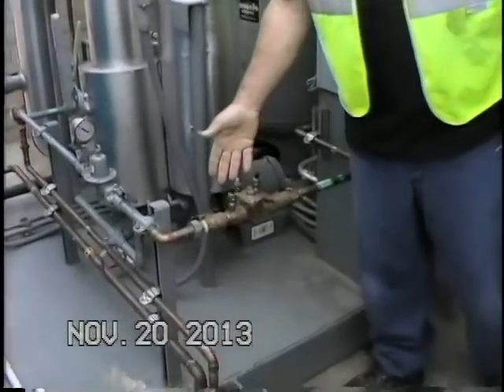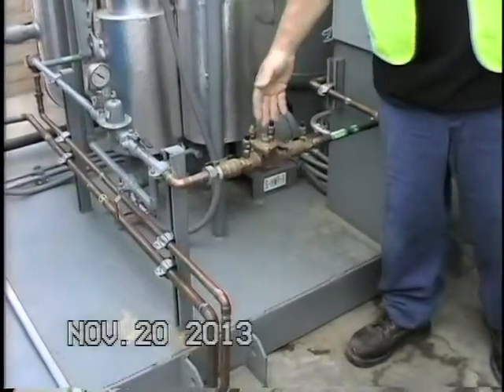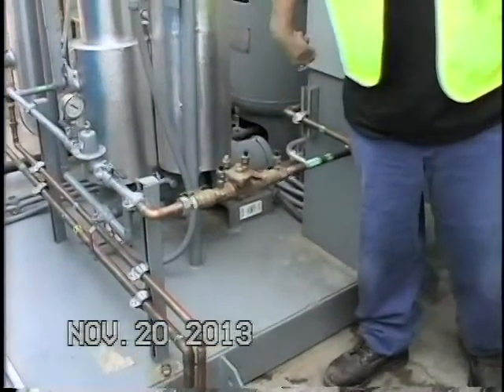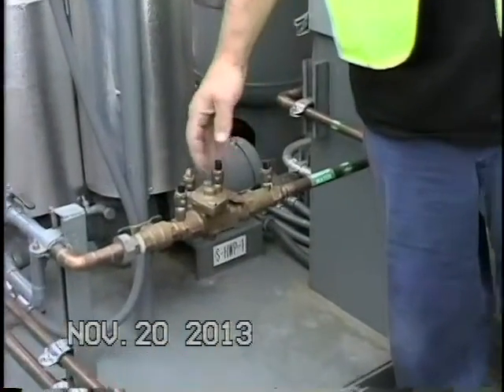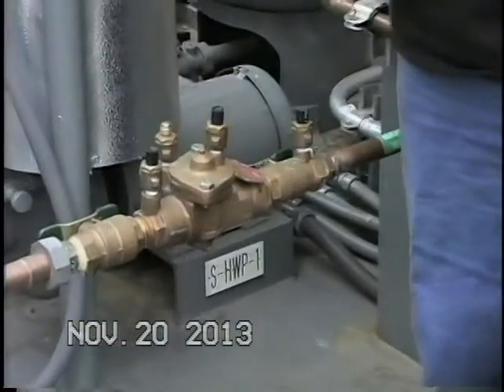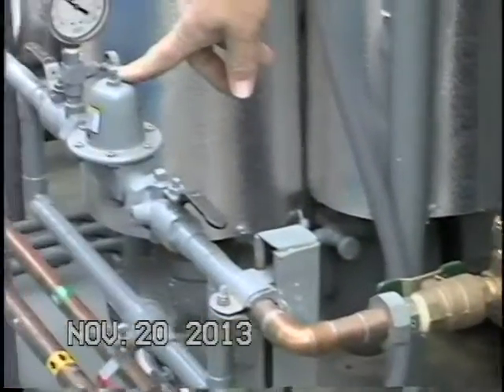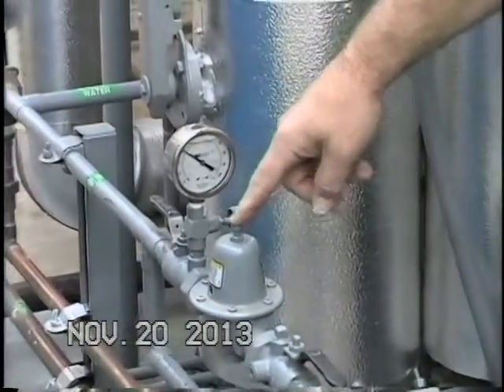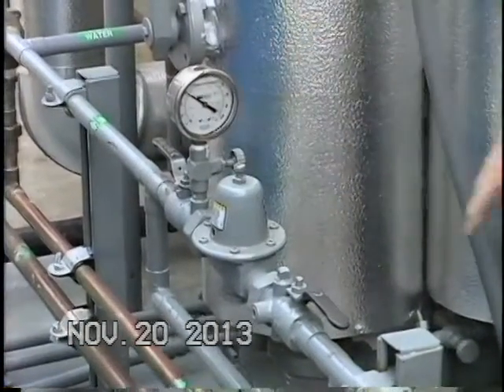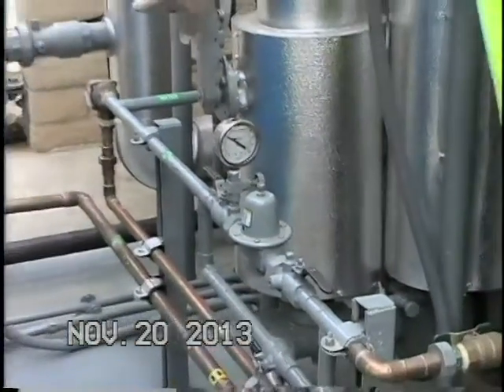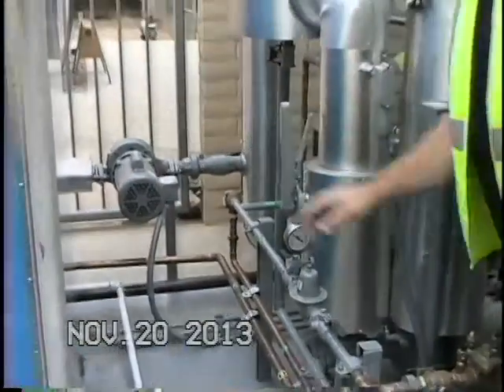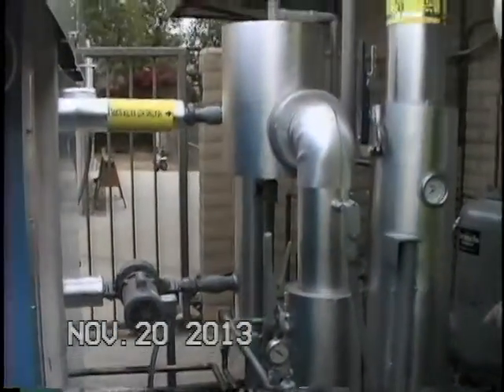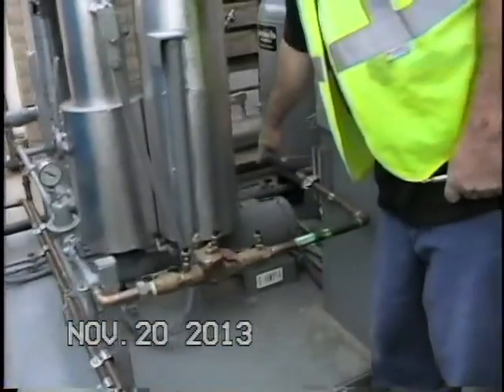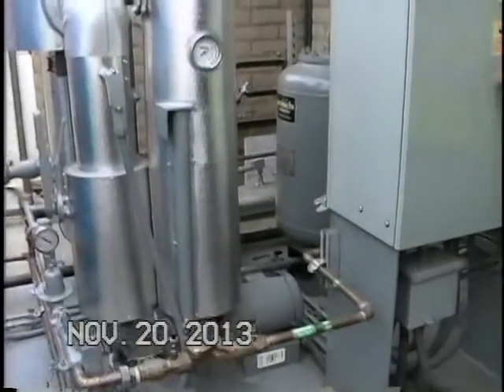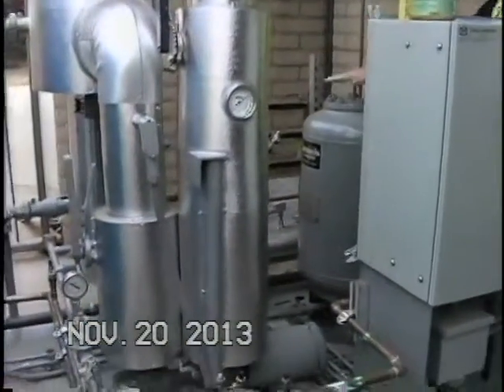This isn't ours, but this is a backflow preventer. Keeps water from the system going back into your city pressure. This is your makeup water. You set your pressure right here on this little top. It's all been set. You have a relief valve over there. You have your system pump here. On this side, you have your expansion tank.